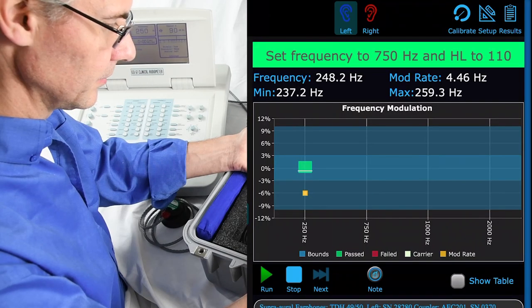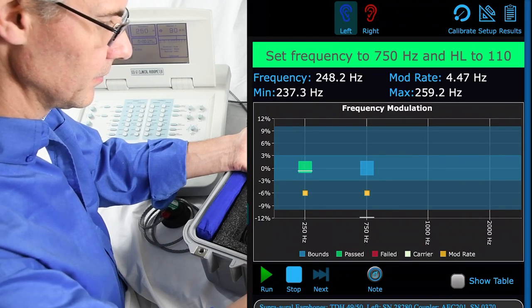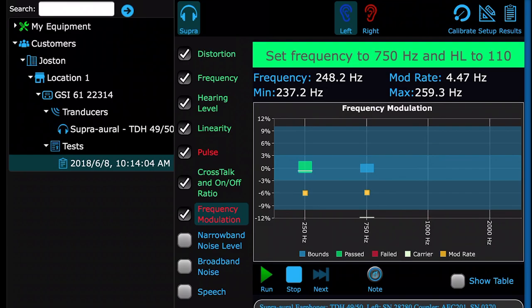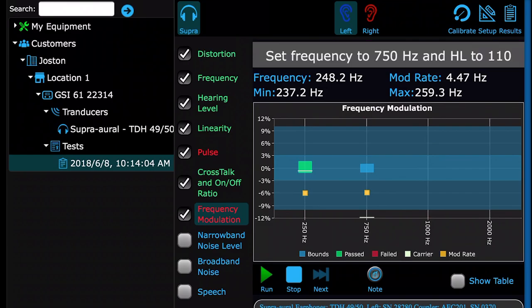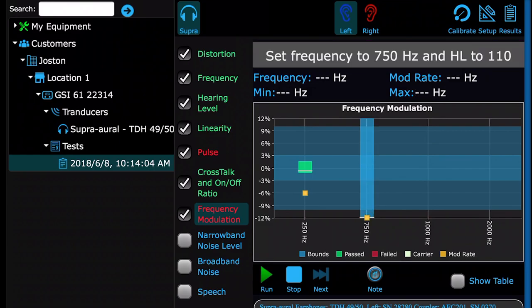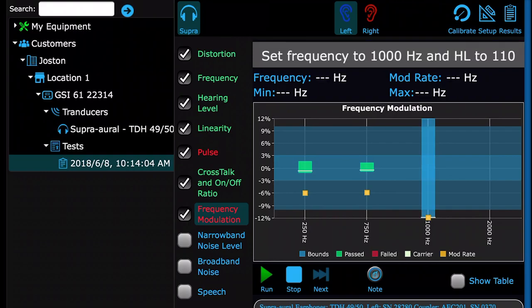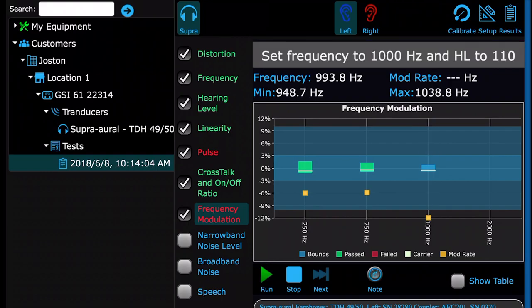Lastly, there is frequency modulation. The detected signal will need to be within the cerulean portion of the graph to pass. For more information on this test, refer to the manual, but more importantly the standard that you are testing to.